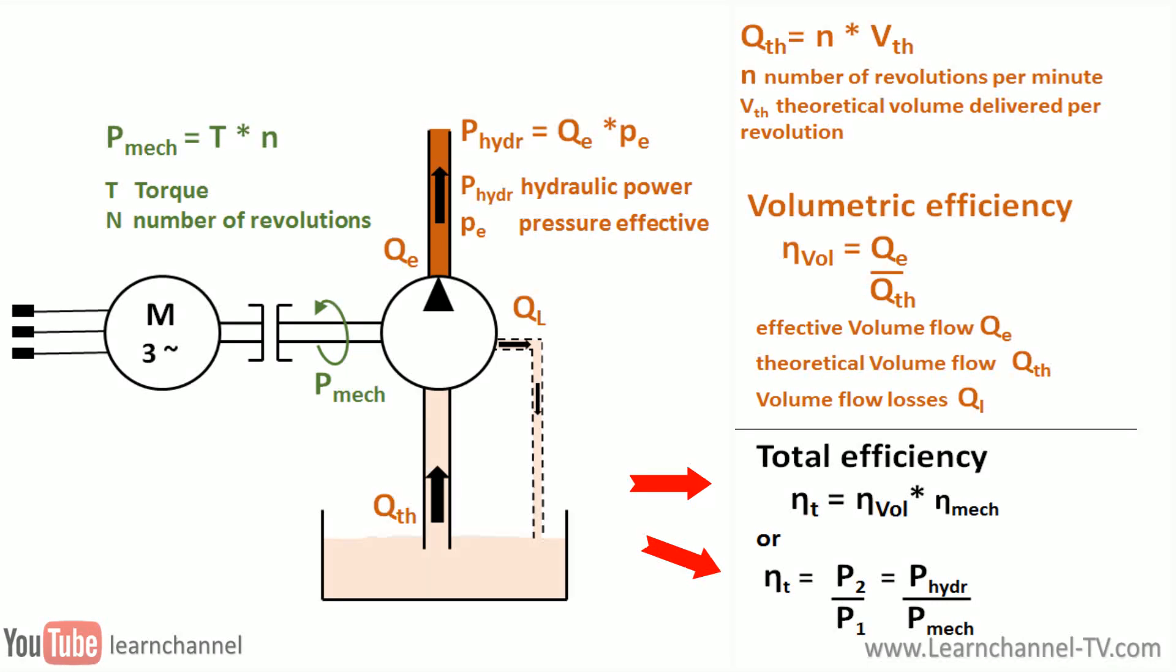So the total efficiency can be determined by two ways, either via the multiplication of the mechanical and the volumetric efficiency, or via the relation between output and input power of the pump.